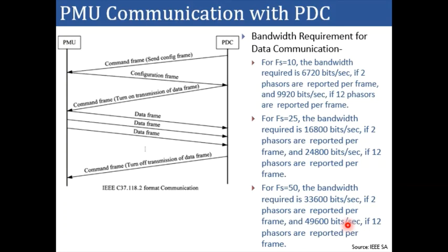Now if we have say thousands of PMUs, let's take the example of India. Right now we are in the process of deploying 1700 PMUs at various buses. Then if we compute the data reporting requirement, you can simply check that if you multiply 50 by 1700, it will be close to 85,000 kbps of speed.